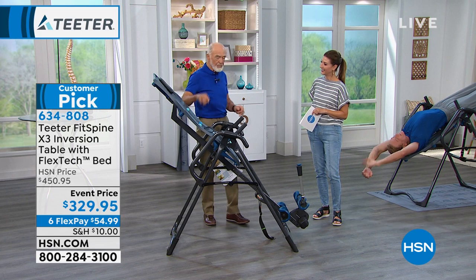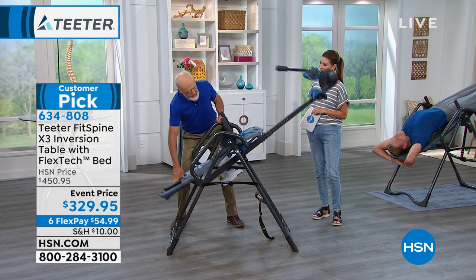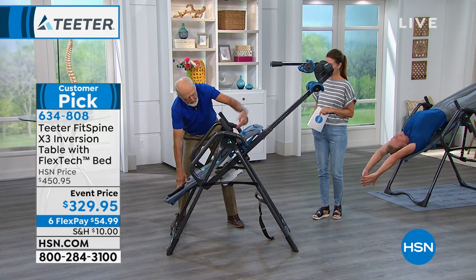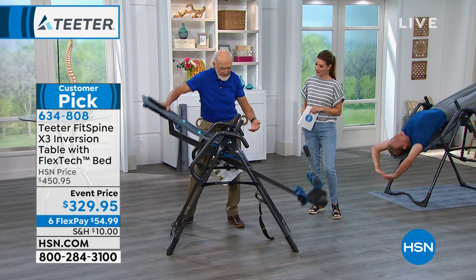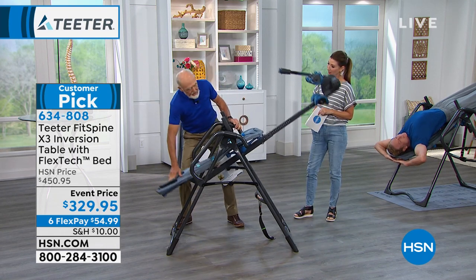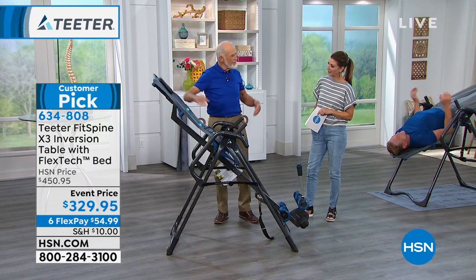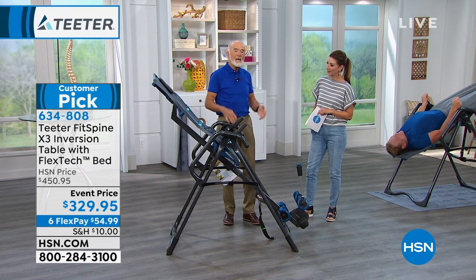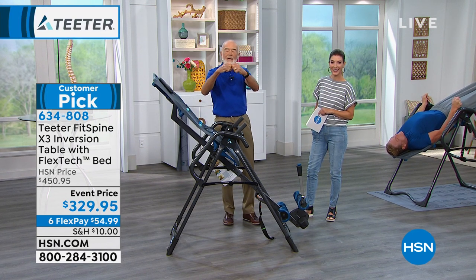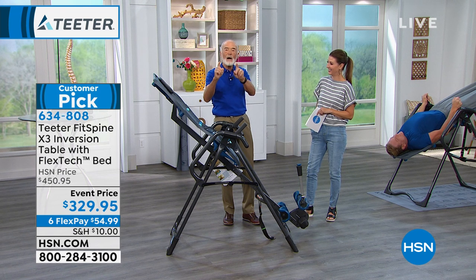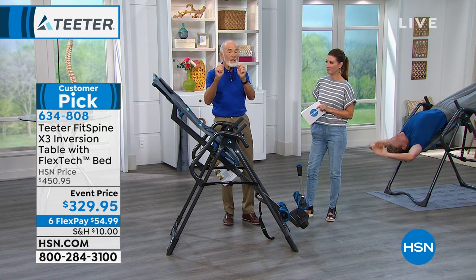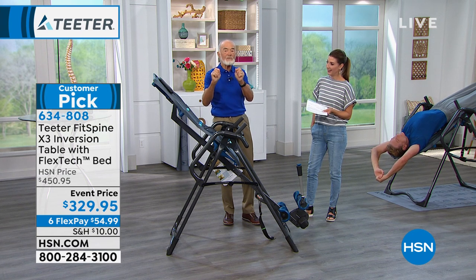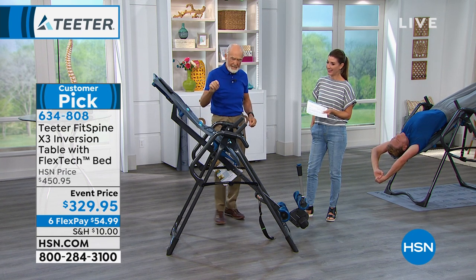That's the problem. When you cycle a table, first these little arms are loaded towards your head, then they're loaded towards your feet, back and forth, lots of people cycling 20, 30, 40 times. Take a wire coat hanger and bend it back and forth, you can break it in 1 minute. That's a fatigue failure, and that wire is ordinary steel. That's what every other inversion table uses, not Teeter.